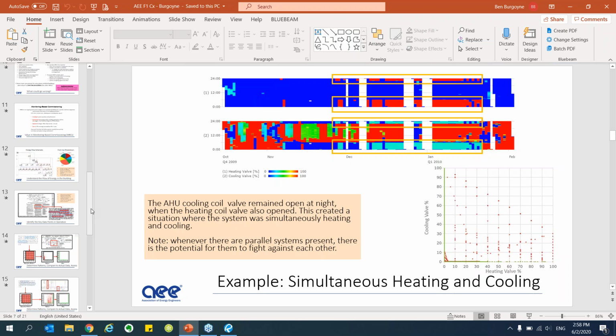So the bigger savings from adjusting room temperature based on occupancy come from adjusting it for the nighttime, in terms of going a good 10 or 12 hours with a less demanding set point. But that can be implemented through scheduling on the building automation system. It doesn't necessarily require occupancy sensors, but I have seen them implemented. Actually, it's helpful in spaces that are not so frequently occupied, like conference rooms.